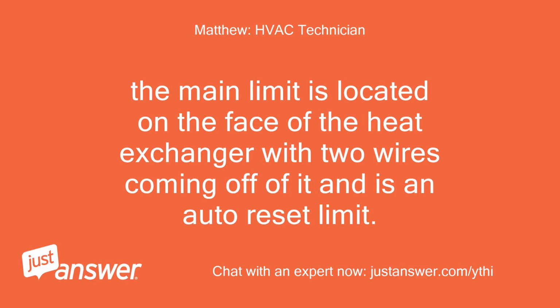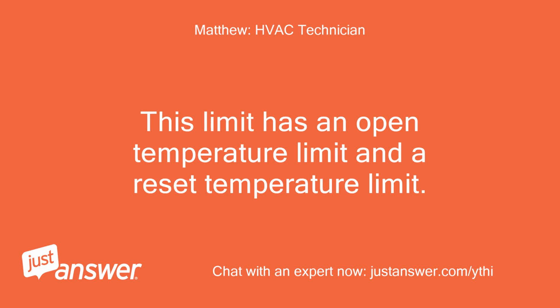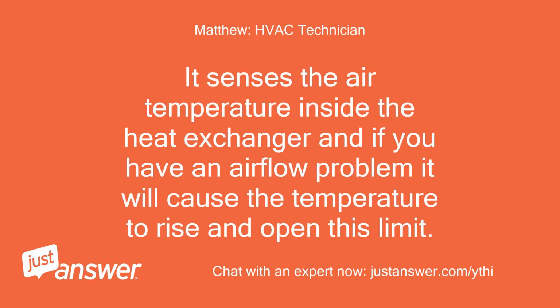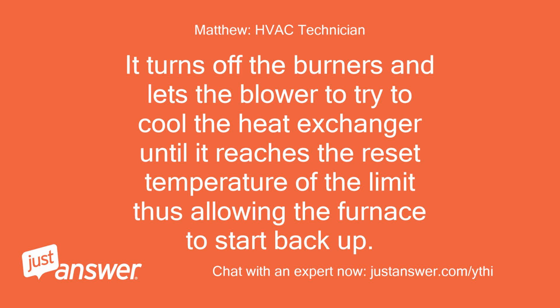The main limit is located on the face of the heat exchanger with 2 wires coming off of it and is an auto reset limit. This limit has an open temperature limit and a reset temperature limit. It senses the air temperature inside the heat exchanger, and if you have an airflow problem, it will cause the temperature to rise and open this limit. It turns off the burners and lets the blower try to cool the heat exchanger until it reaches the reset temperature of the limit, thus allowing the furnace to start back up.